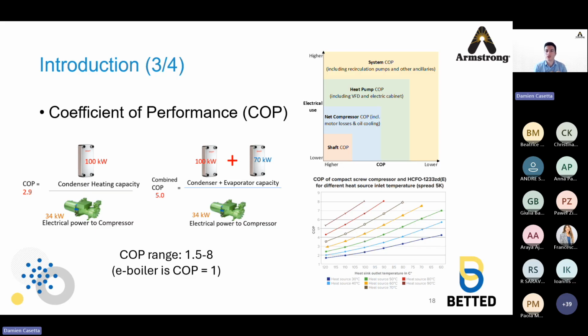In the scope of this electrical power, you have various definitions: from shaft COP, which includes only the mechanical power to the compressor, then compressor COP, which accounts for the motor losses, then heat pump COP, accounting for all electronics, and system COP. That's really what reflects the OPEX for the customer, as it accounts for all the pumps and ancillaries that are required to make it work. So it's important to keep this in mind when you are analyzing the numbers.